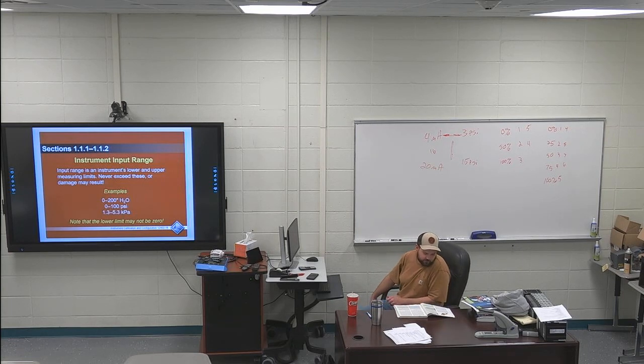112, output signals or energies. First sentence of that is highlighted. Output signals or energies from an instrument are proportional to the input signals and represented accurately. So that's just what I was saying on the board: 4 milliamps would represent 3 psi, 20 milliamps would represent 15 psi, and so on and so forth.